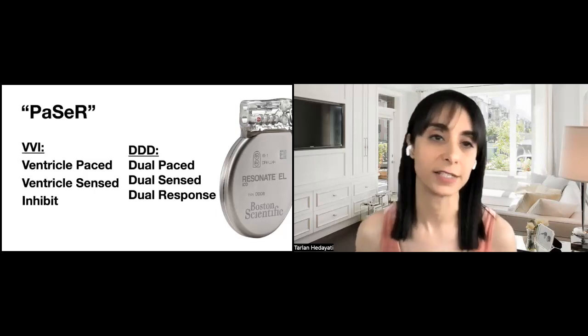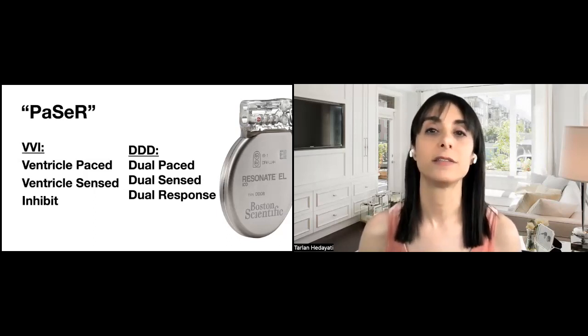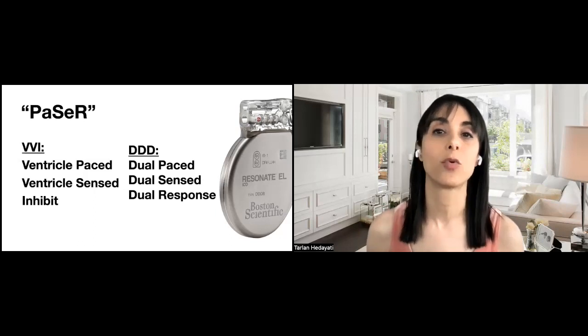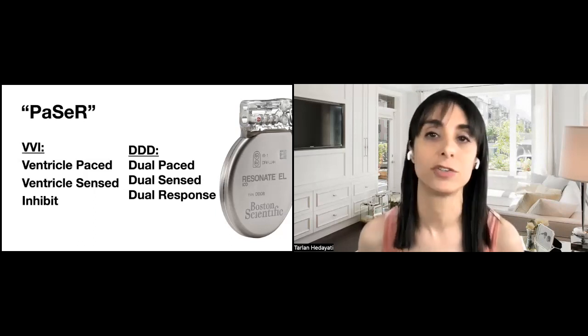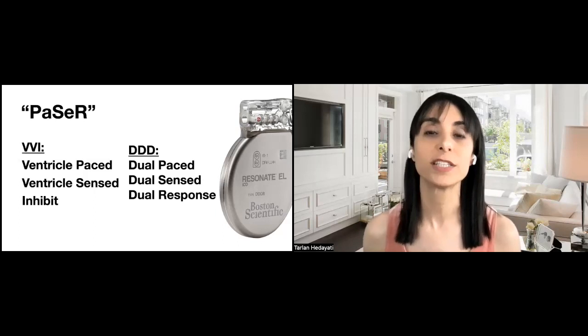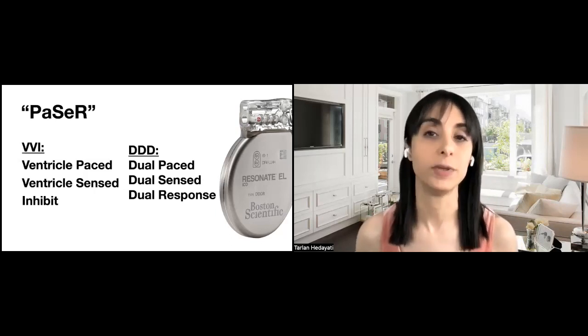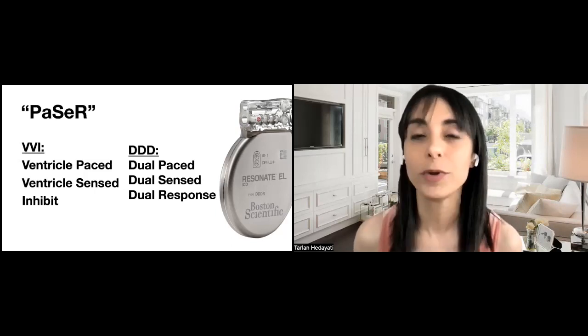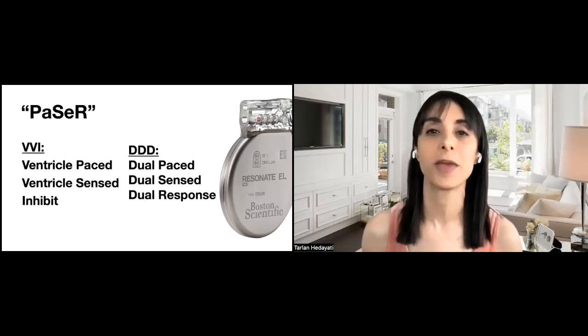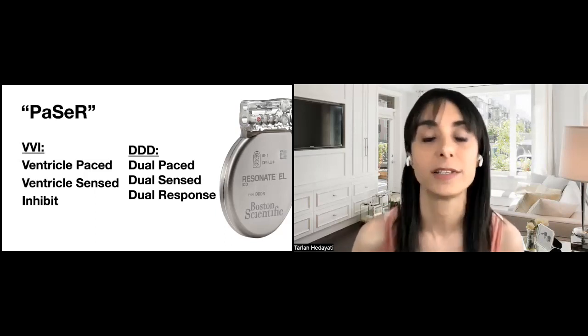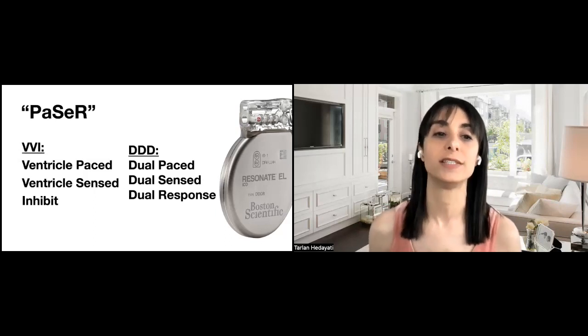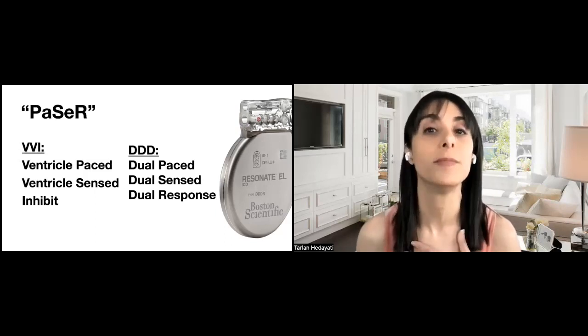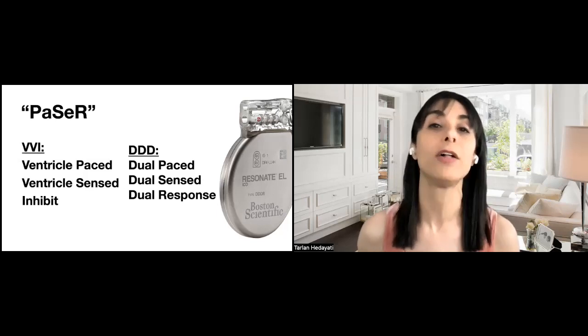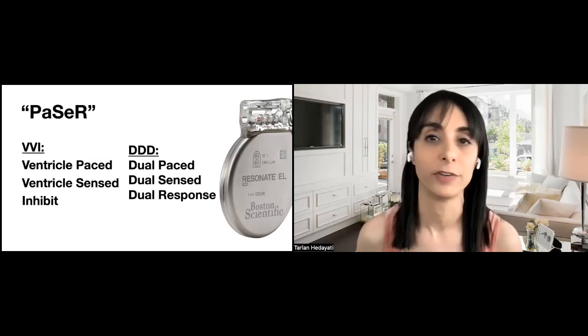That's what sensing is. And then the last thing is the response, so the pacemaker or the ICD has to respond to what it sees. Essentially we want the pacemaker, in an ideal situation, to be triggered to do something if it needs to be done, or if the heart's doing okay and doesn't need the pacemaker or ICD, we don't want it working. So we want the device to inhibit itself and not do anything, and that helps preserve the battery life.